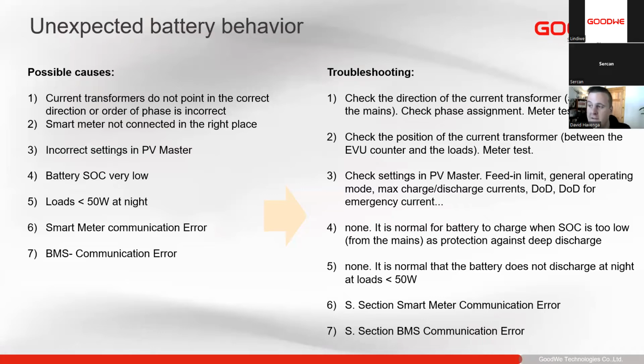Next, if our loads are less than 50 watts, the battery does not start to discharge, especially if we are using zero export. When we have less than 50 watt load at night, the battery won't discharge for that 50 watts. And then lastly, if there is a communication error with the smart meter or the BMS.